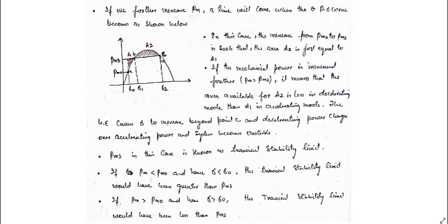At this point, the speed is not equal to synchronous speed. It is slightly greater than synchronous speed. Delta continues to increase. When delta increases, Pe would normally increase, but here Pe actually decreases because delta is greater than 90 degrees. When it decreases, accelerating power also increases.